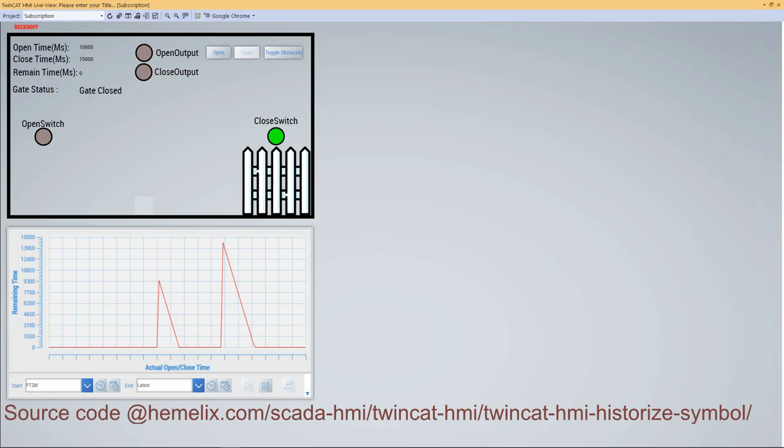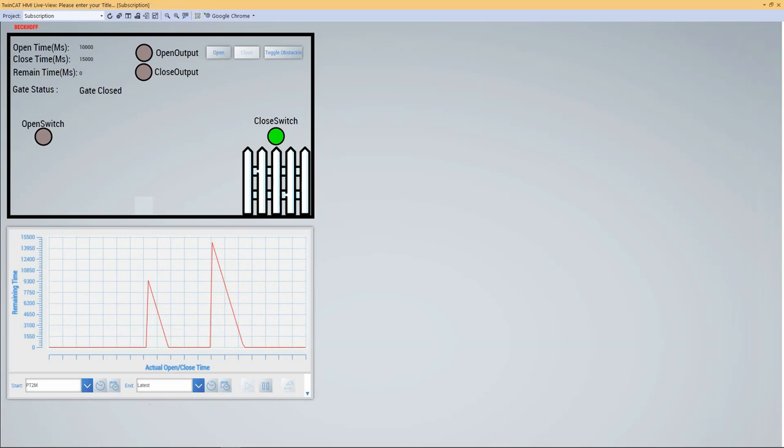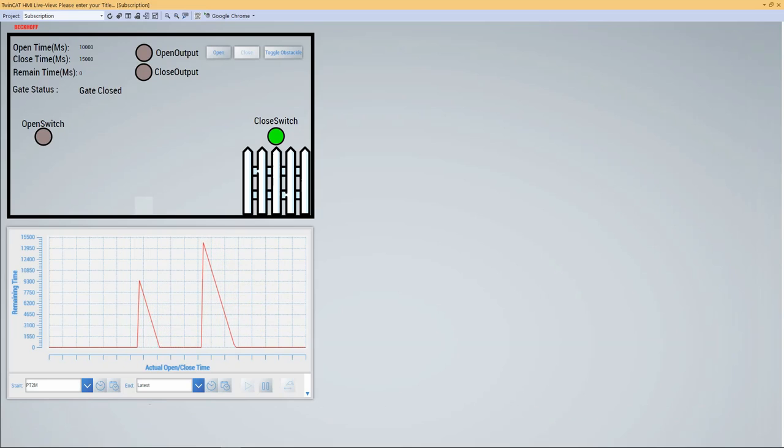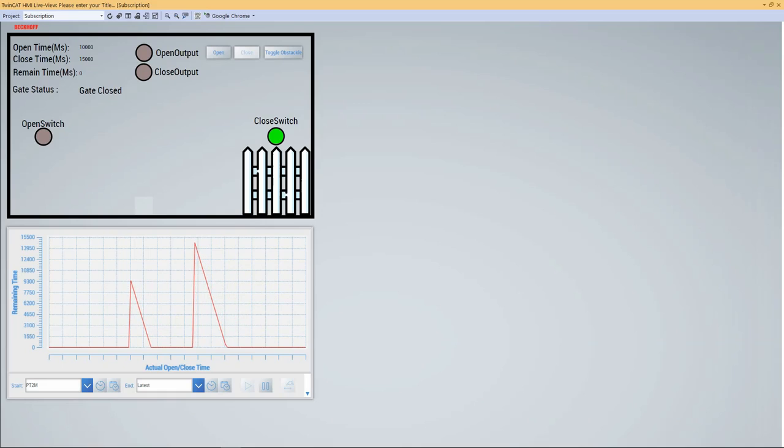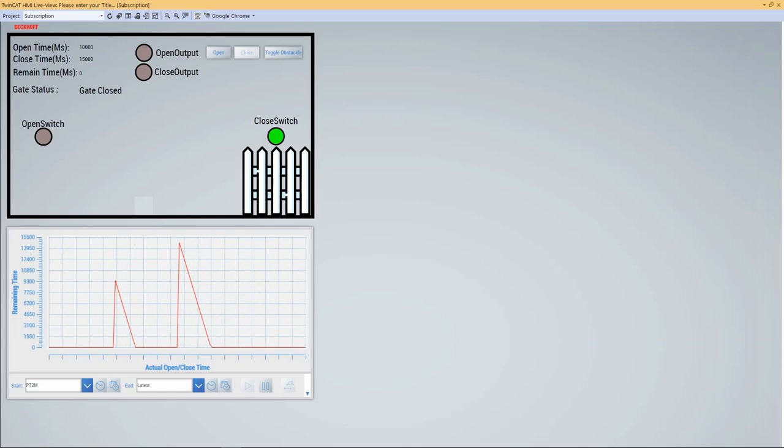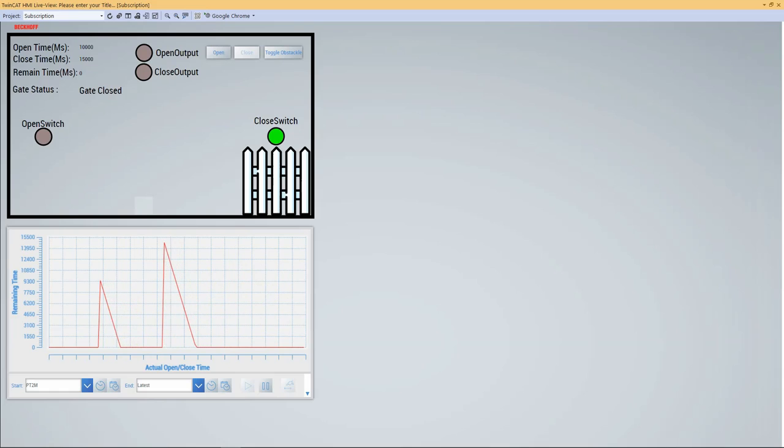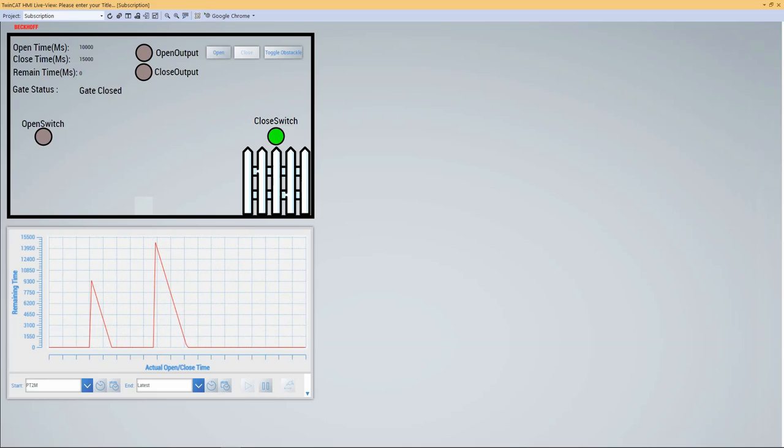Some software systems clearly define event and data historian separately. Arbitrary server symbols of the TwinCAT HMI can be historized by the TCHMI SQLite Historize extension. The extension saves the data in a ring buffer in an SQLite database. The interval at which data are saved in the database can be defined for each symbol. The historical data are displayed in a control called trendline chart, which enables the display of various historical data at the same time.